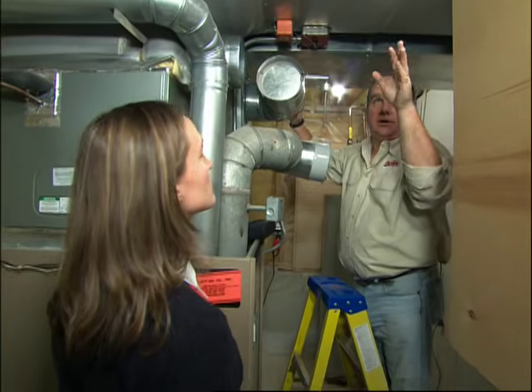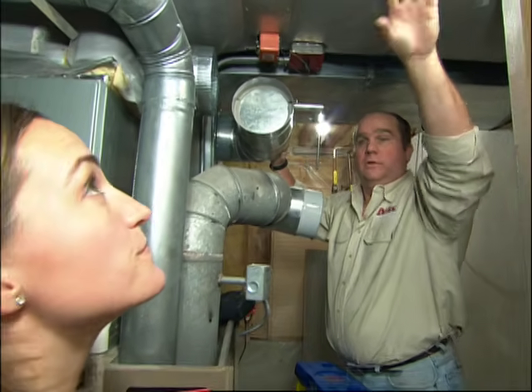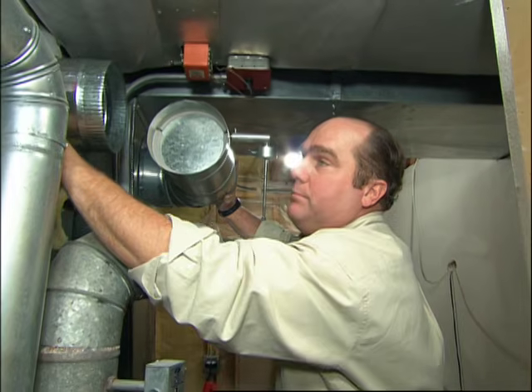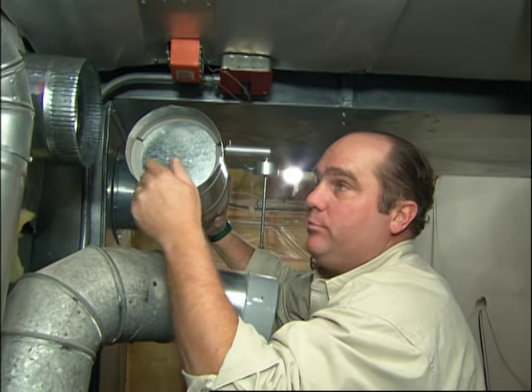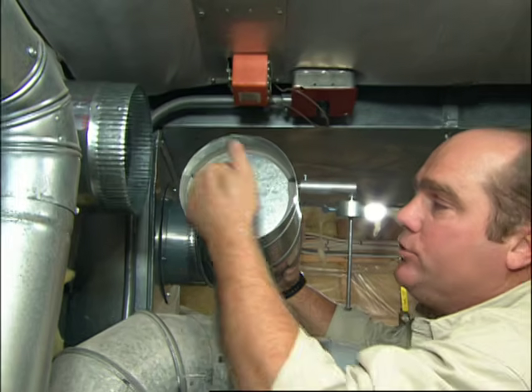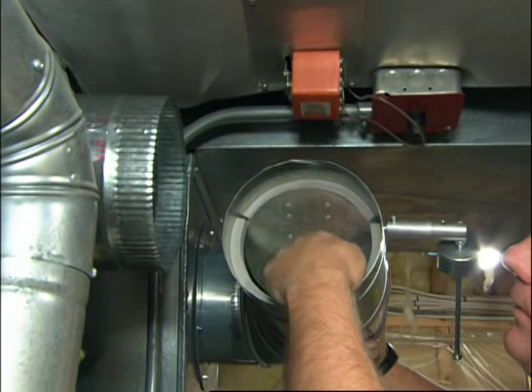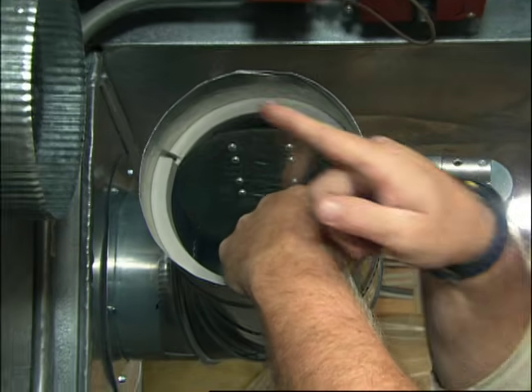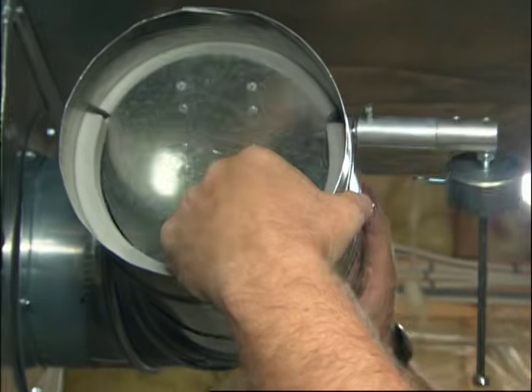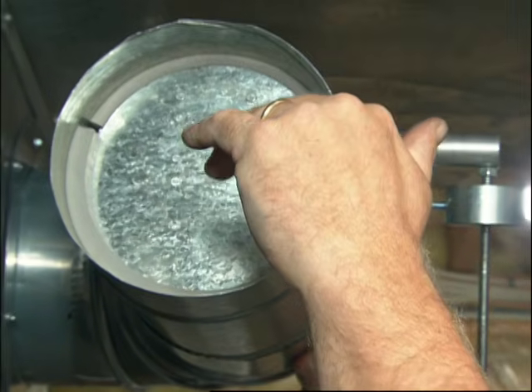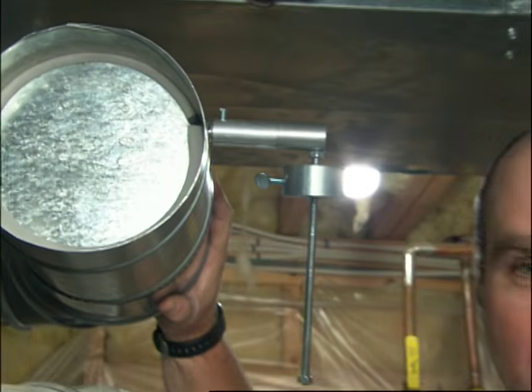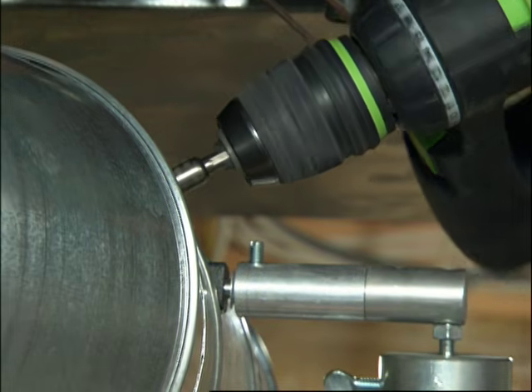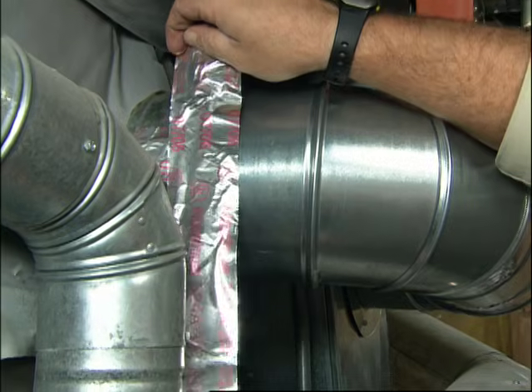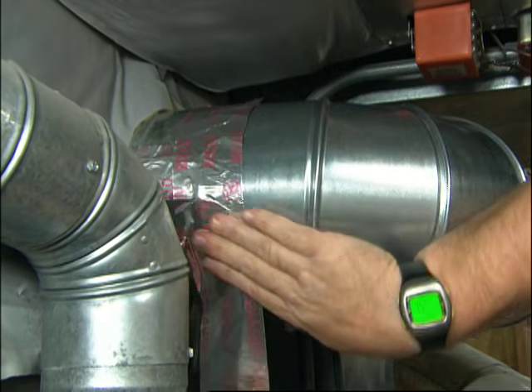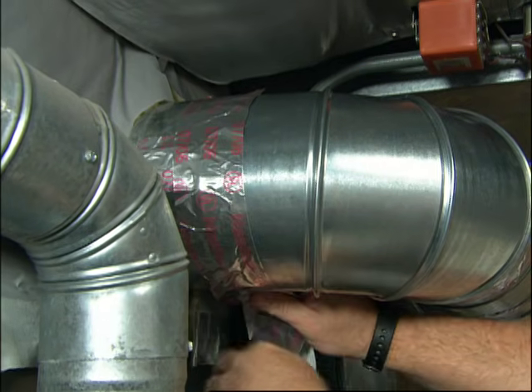When you have that condition you talked about, closing that first floor zone, you build up the pressure here in the supply plenum. Now we have a way to relieve the pressure. That higher pressure air pushes and can open this door. Now that air can divert between the supply and the return. Now what that does, it drops the pressure over here. You're no longer pushing against that closed damper, no more whistle, no more annoying noise. I like to use some foil tape to seal up these seams.